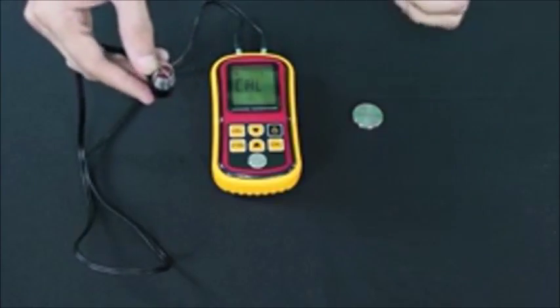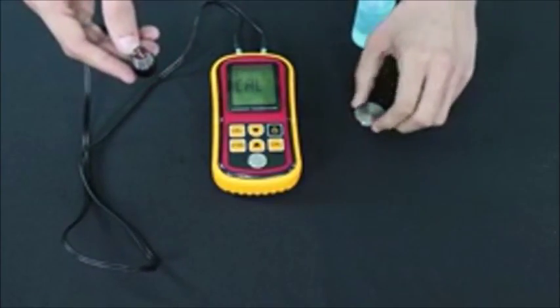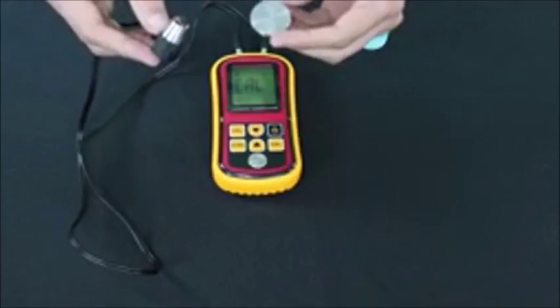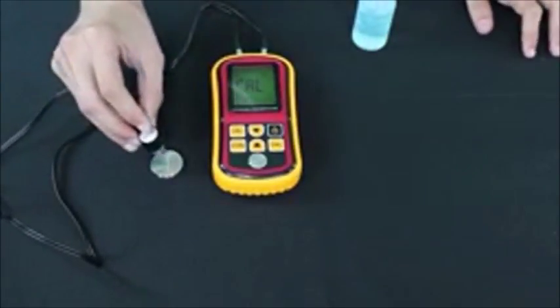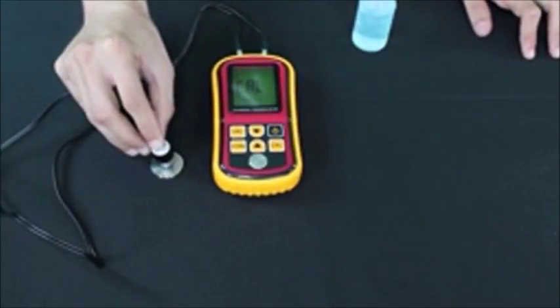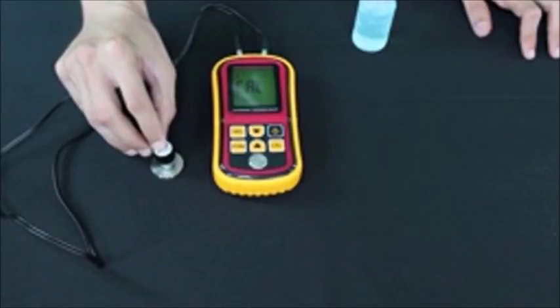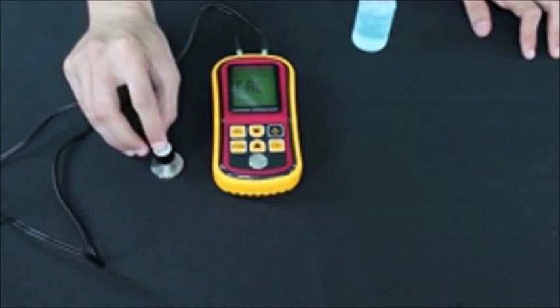First thing you want to do is turn on the thickness gauge by pressing and holding the power button. This is the startup screen. You're going to have to let it go all the way through and we'll start calibrating. Alright, we've got to the main page.